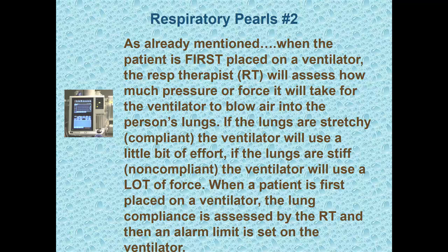So let's say that the peak pressure, which just means how much force has to go in, is somewhere in the 30 range. The respiratory therapist would set that alarm a little bit higher, so around 40, or lower, say 20. They usually set it 10 above or 10 below. These may vary depending on the therapist.